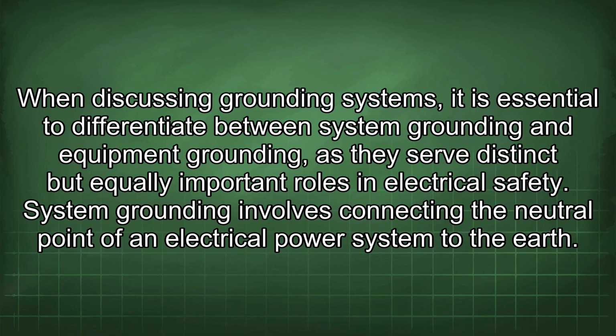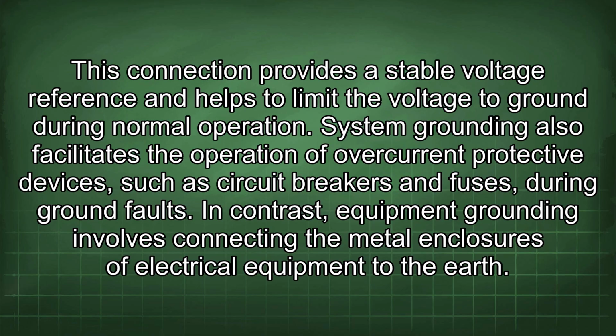When discussing grounding systems, it is essential to differentiate between system grounding and equipment grounding, as they serve distinct but equally important roles in electrical safety. System grounding involves connecting the neutral point of an electrical power system to the earth. This connection provides a stable voltage reference and helps to limit the voltage to ground during normal operation. System grounding also facilitates the operation of overcurrent protective devices, such as circuit breakers and fuses, during ground faults.